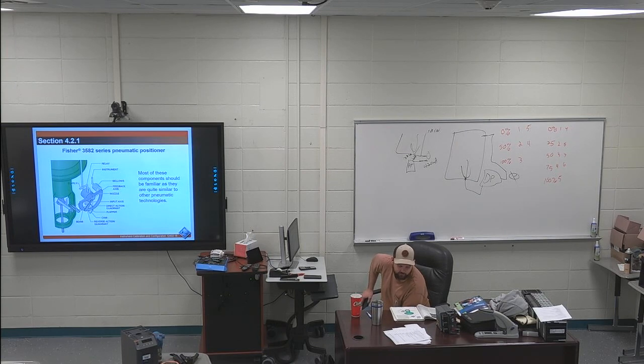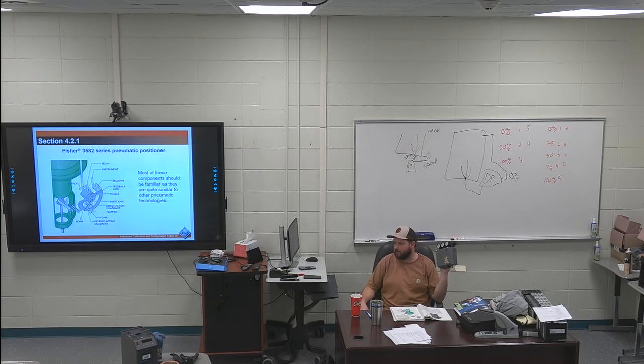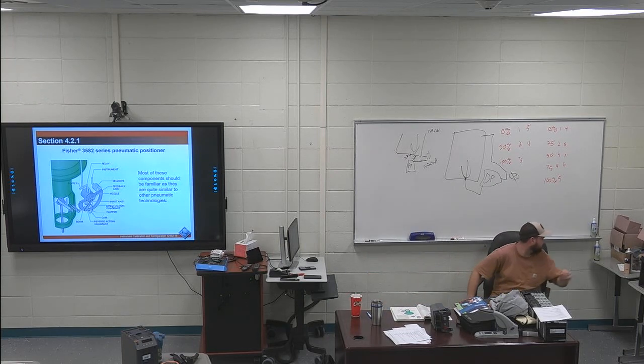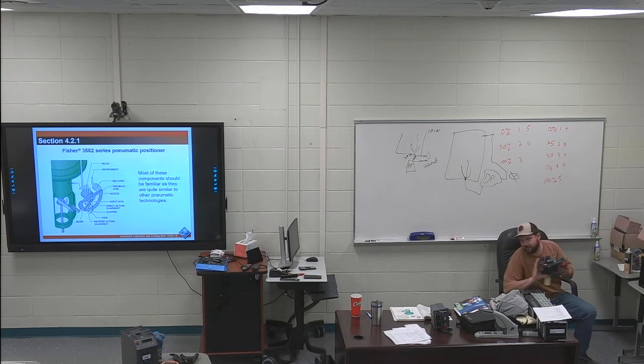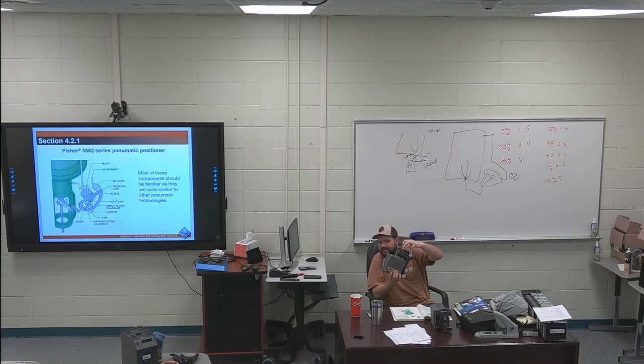Electro-pneumatic valve positioners are very similar to purely pneumatic positioners, except that a DC current signal is received by an electro-pneumatic signal converter or transducer attached to the positioner. This is just the input to this is pneumatic. So whatever signal is coming from the control room is going pneumatic into this, and then they're putting that into the valve. This one is an electro-pneumatic positioner and sends a DC signal into this, and then that converts it into whatever the PSI needs to be for the valve. So you can have different ones of these as well.